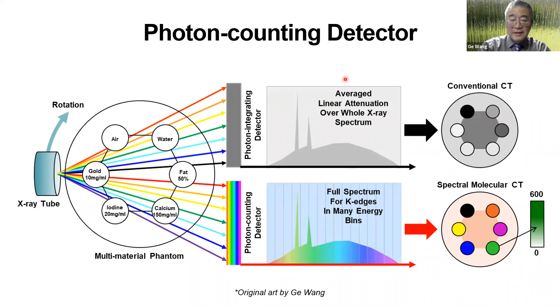Equally important, you not only have spectral information, you can also make the detector element much smaller. Right now, there is a photon-counting detector with a 55 micron pixel, and you can use it in 2x2 binning. You get 100 micron resolution. So this kind of detector element allows us to significantly improve clinical CT image resolution from the current best of around 200 microns, by several fold. We can target around 50 microns. So this is micro-CT resolution. So the photon-counting detector is an enabling technology.